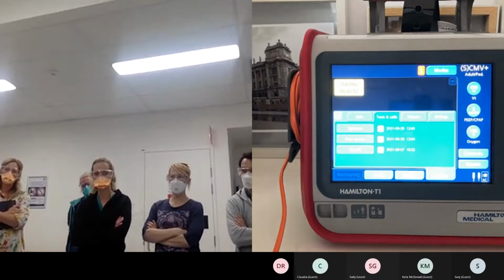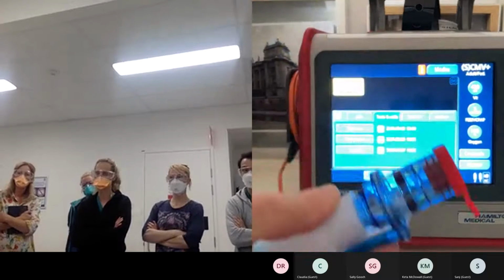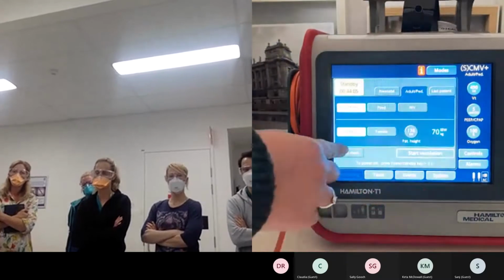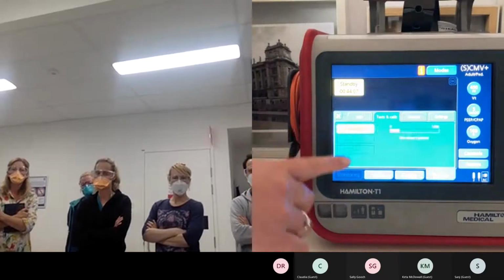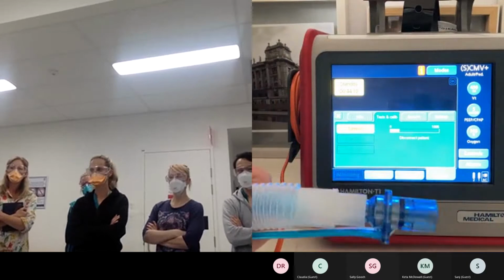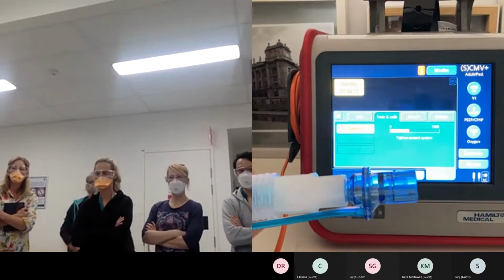Okay. With the tightness test, this is like a leak check. The circuit, when it first comes out of the pack, comes with a red cap on the end. So what you do is touch on tightness, it tells you to disconnect patient, so you take that red cap off. Then it will tell you to tighten patient system, so you pop your cap back on.